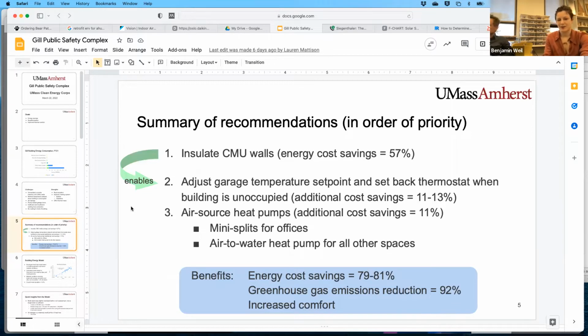So here's a summary of our recommendations. Top priority is insulating the walls, which will lead to an energy cost savings of 57% and also enable some other changes. The second recommendation we're making, once the CMU walls have been insulated, is to adjust the garage temperature set point and set back the thermostat when the building's unoccupied. And this will provide an additional cost savings from 11 to 13%. And this setback is a change that can be made without actually spending money on it. So you start realizing the benefits from that immediately without any payback period.